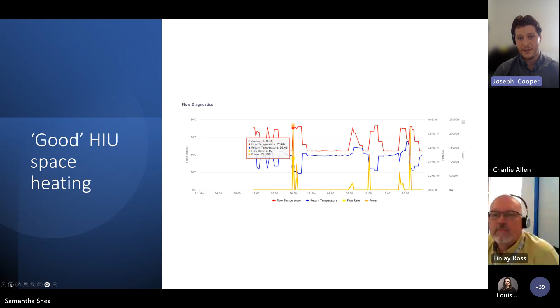So, benefits of changing to a direct connection with the new HIUs: the optimisation report showed us there would be a lower HIU cost, a more efficient system operation with higher plant efficiency and lower heat loss, a longer life for heating system components in apartments such as radiators and TRVs, and reduced maintenance for the HIU and apartment heating systems, meaning no more leaks or failing components. It would also allow us to install a much simpler HIU required to enable weather compensation.